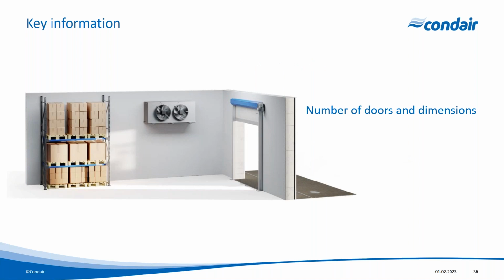How many doors are there? What is the actual operating area of the door? So just because the doorway is X by Y, actually the opening may be smaller than that. And the really critical one, how often are those doors open? This is the really tricky one. Have you got a really robust regime in your cold store that's going to make people close the door? Or are they propping the door open, worst case scenario? Have they got a good regime that if they're opening that door, they've used it, they're closing it as quickly as possible?